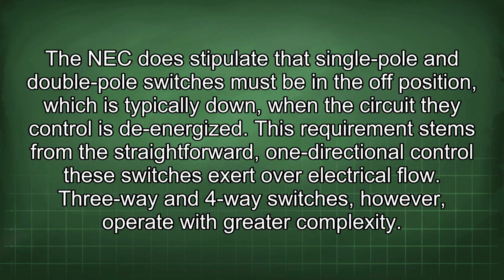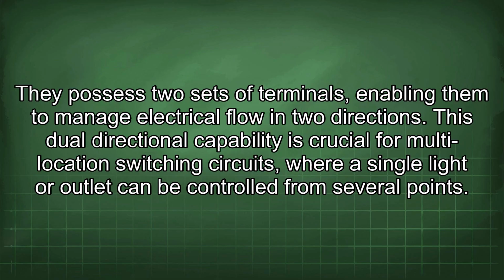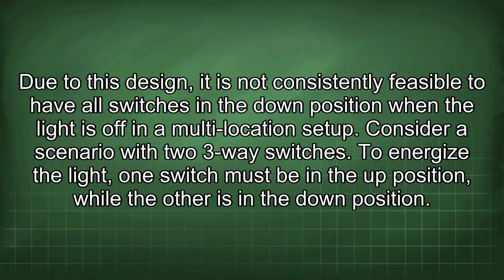This requirement stems from the straightforward, one-directional control these switches exert over electrical flow. 3-way and 4-way switches, however, operate with greater complexity. They possess two sets of terminals, enabling them to manage electrical flow in two directions. This dual-directional capability is crucial for multi-location switching circuits, where a single light or outlet can be controlled from several points. Due to this design, it is not consistently feasible to have all switches in the down position when the light is off in a multi-location setup.